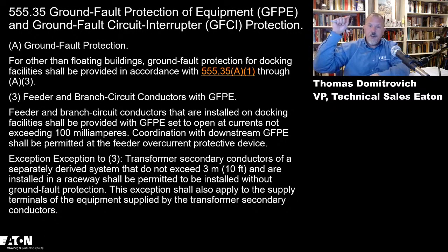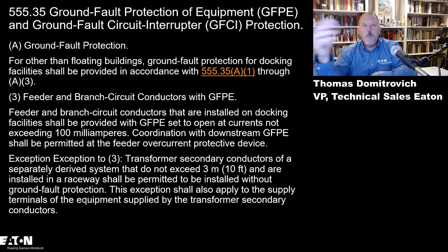So a feeder, now we're moving up in the power distribution system. We're moving from that branch circuit receptacle that's feeding the boat, or the branch circuit receptacle that's feeding your power supply for your tools and whatnot. Now we're into the feeder. And the feeder has to be protected at 100 milliamps. Now, I know that there was a debate. People didn't like 30 milliamps. We actually had a couple people say that there are marinas working at 30 milliamps.